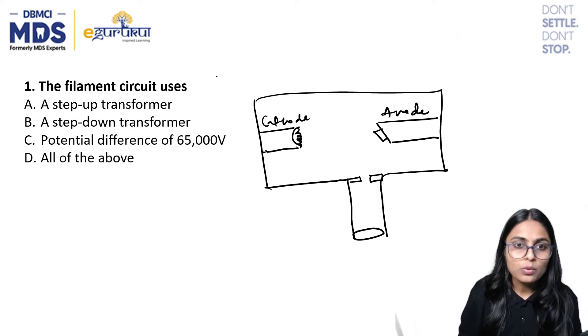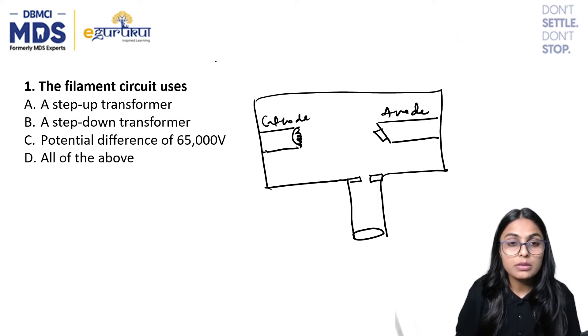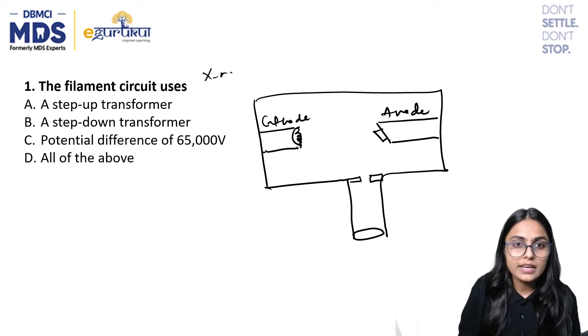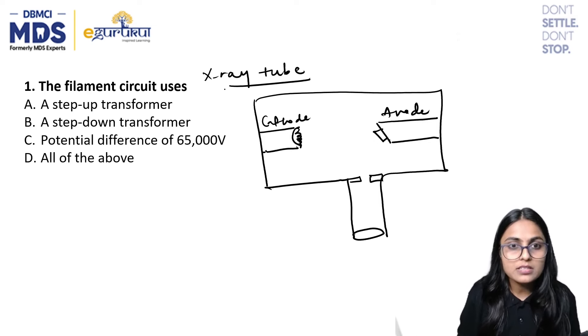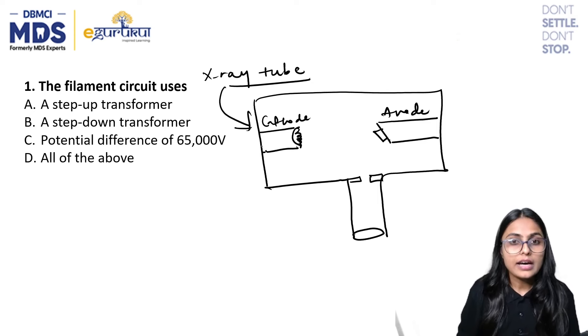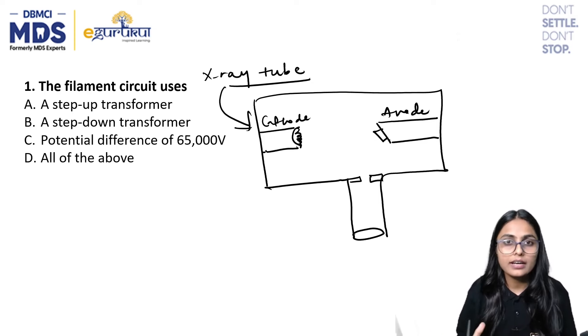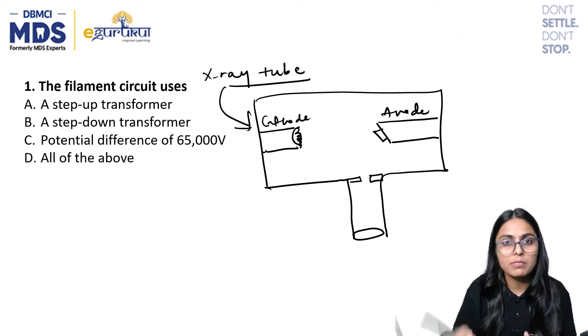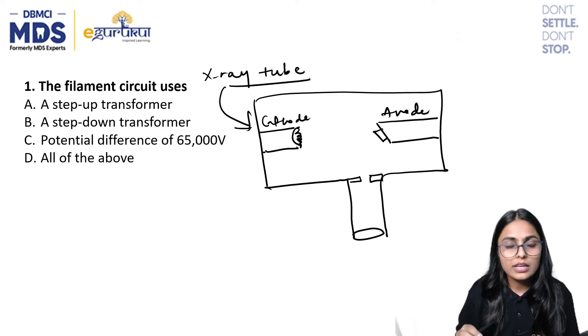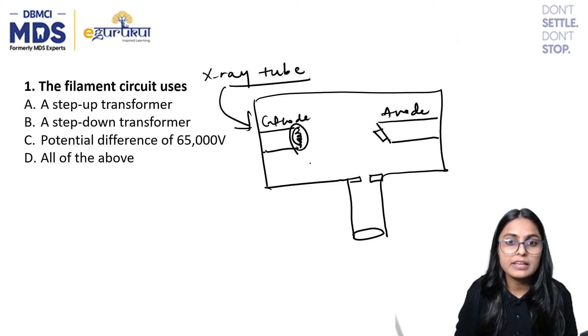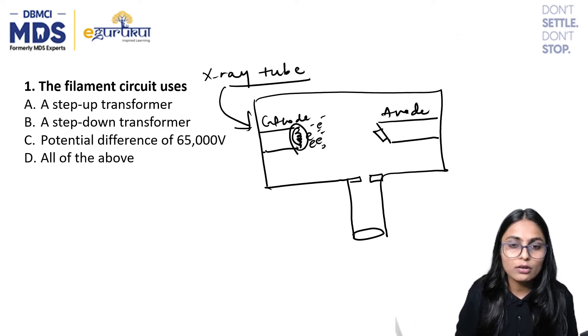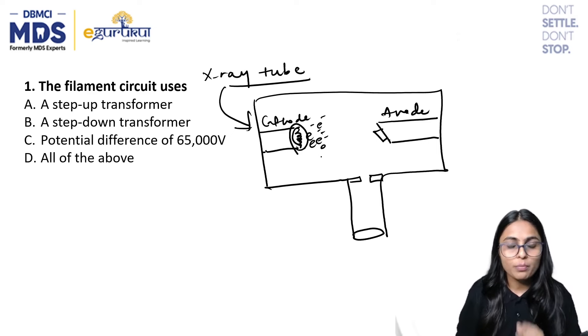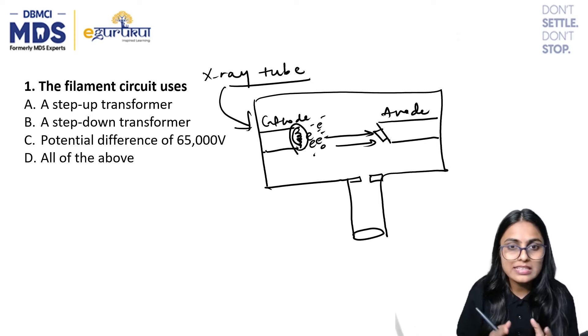When we studied X-ray production — when you switch on the X-ray tube, what exactly happens is current flows through the machine. We set up kilovoltage and current, and exposure time. This milliamperage is required to heat up the filament. When you switch on the X-ray tube, the filament is heated and an electron cloud is formed around this filament.